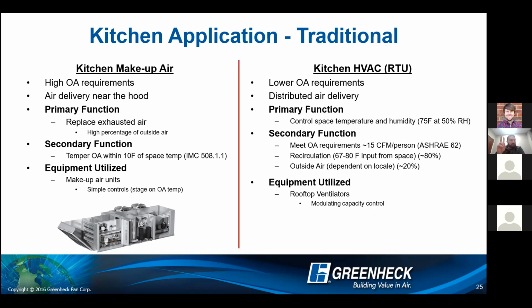It can be laid out this way with a traditional makeup air unit and a rooftop unit. I think we've already touched on this, but the primary function of the kitchen makeup air unit is just to replace that exhausted air with a high percent of outside air. If we're heating and cooling, it's to temper that within 10 degrees of the space. And then your traditional rooftop unit is controlling the space temperature and humidity, and meeting outside air requirements, recirc, outside air, all the things that a traditional RTU is doing.